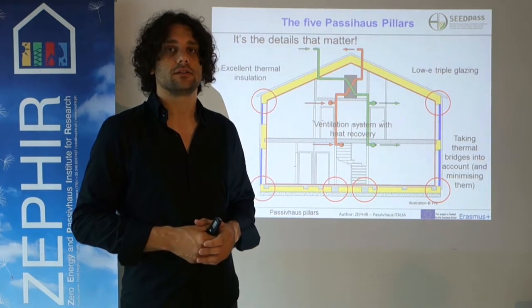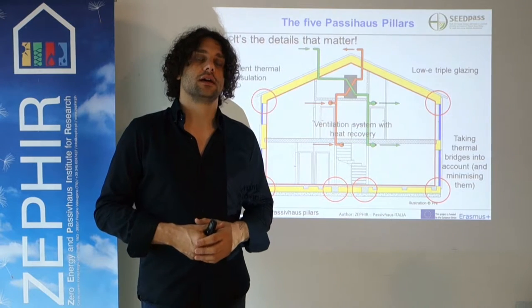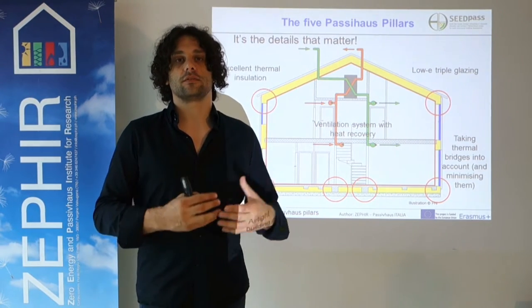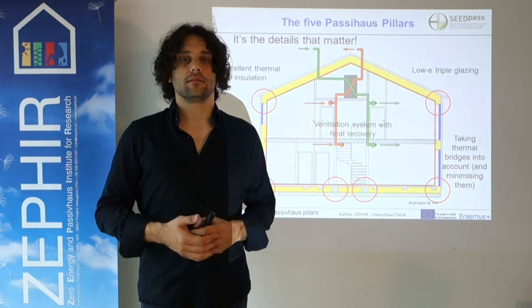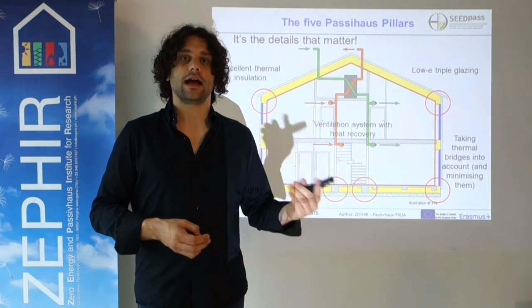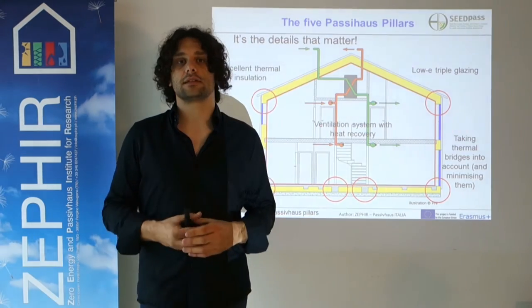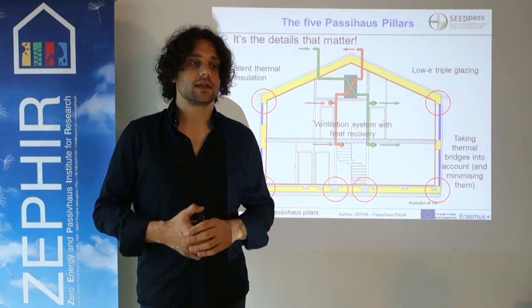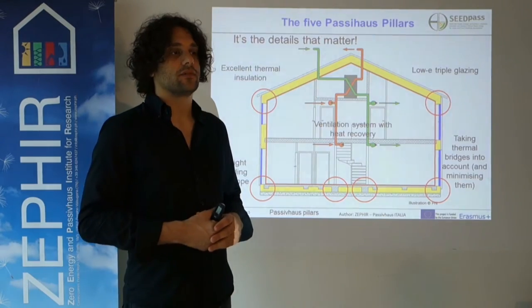In summer, we can and should open the windows, but only if this results in an overall reduction of internal temperature. However, we must also prevent humid external air from entering the building, which would then need to be removed actively. In that case, it may be better not to open the windows, but instead use the ventilation system plus an active cooling system — like a fan coil or split unit — which reduces internal temperature without adding excess humidity that would cause discomfort.